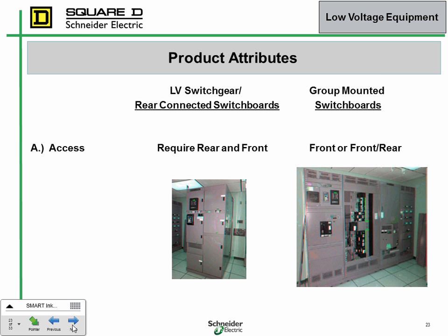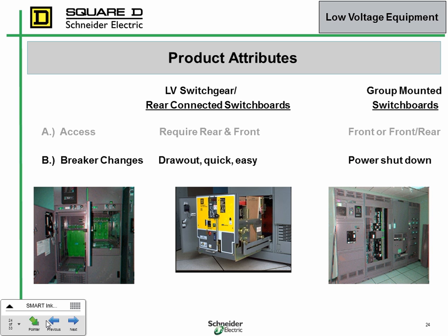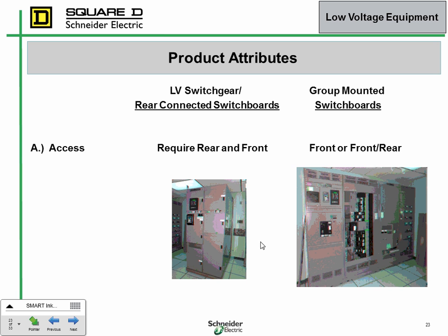Yeah, there you go. So on that picture to the left. Yep, go back. That to me looks like the front, but it doesn't look like there's access. This is front. This is a piece of equipment right here. It's kind of hard to see, but there is actually space. And when we say rear access, it depends on the voltage. You may require 3 feet behind there, 3.5 feet, depending what type of wall it is. If it's block or some type of insulated material, then you can get down to 3 feet, okay?